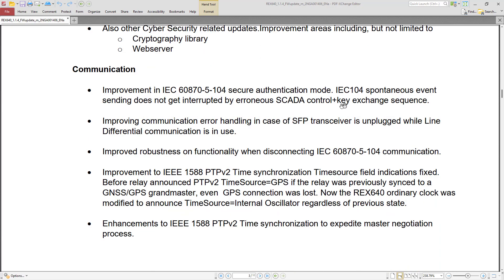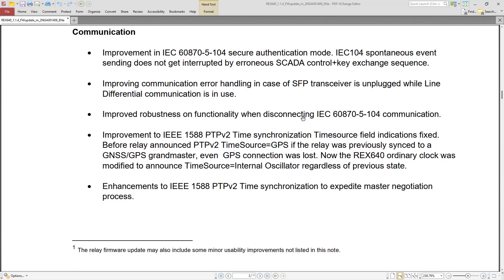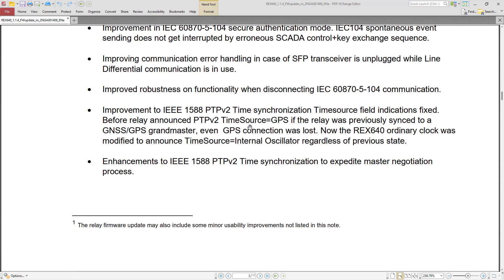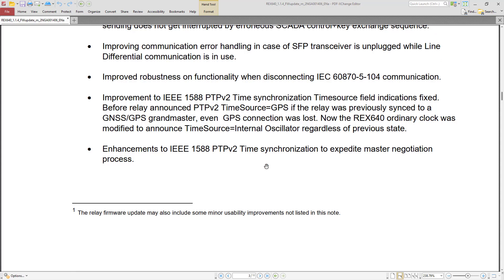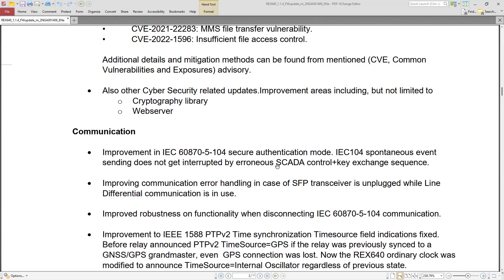There are also improvements related to the IEC 60870-5-104 protocol on this IED, as well as fixes for differential communication. REX640 is a multi-application IED supporting many different protection functions used in medium voltage substations. We can also see improvements related to PTP — Precision Time Protocol — which is very important when working with sampled value applications with REX640.